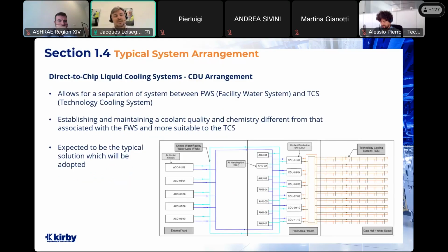All right, so let's look at what a typical system arrangement might look like, and this is just a hypothetical system arrangement. What we can see here in the blue would be a typical chilled water system. A chilled water loop, or as ASHRAE defines it, a facility water loop. So you have your heat rejection equipment in an external yard. That might be air-cooled chillers. Depending on the climate, it could be dry air coolers. If needed, they can be water-cooled chillers.